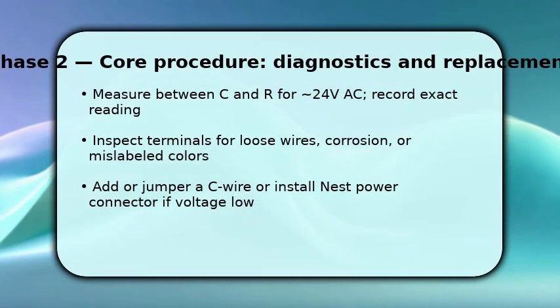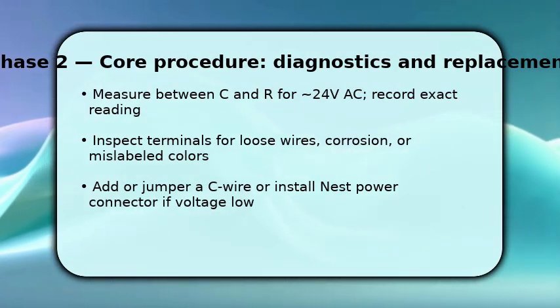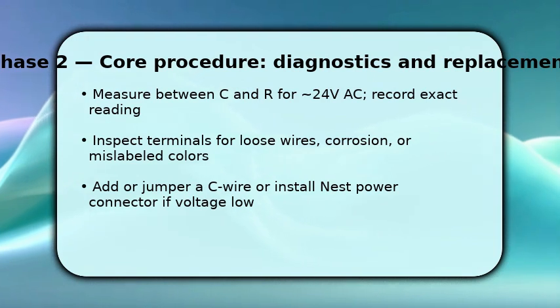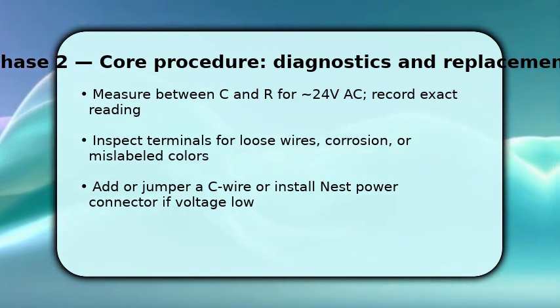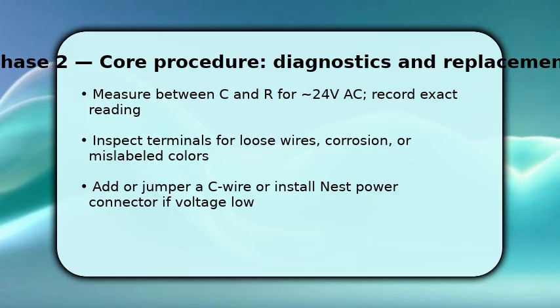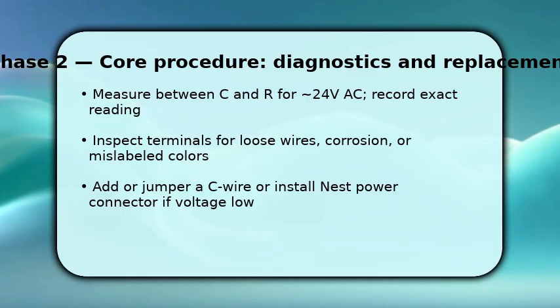Now test the electrical basics. Measure between the C and R terminals for roughly 24 VAC and note the exact reading. If voltage is absent or fluctuating, inspect each terminal for loose connections, corrosion, or swapped wires.